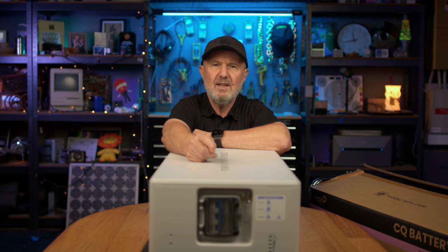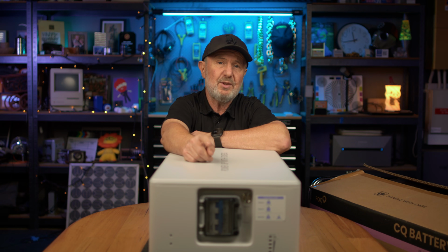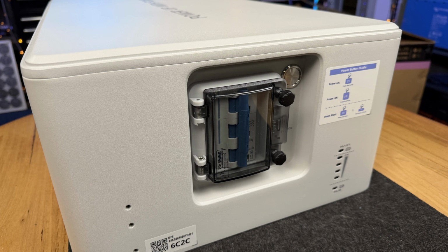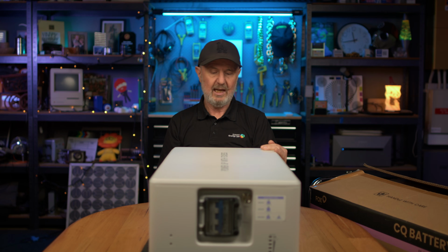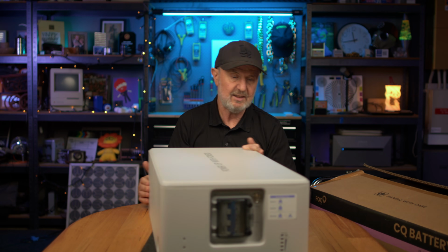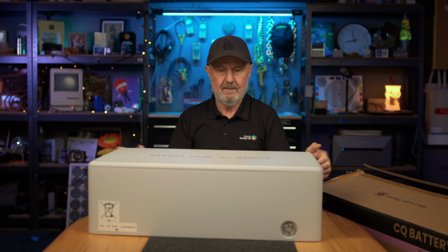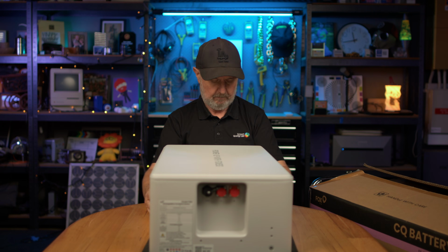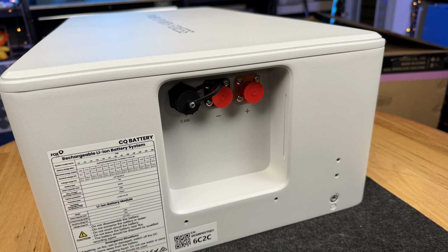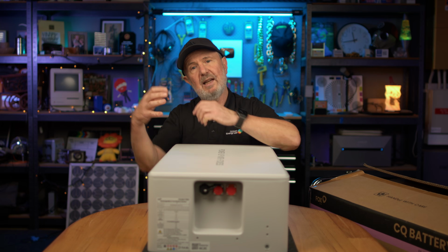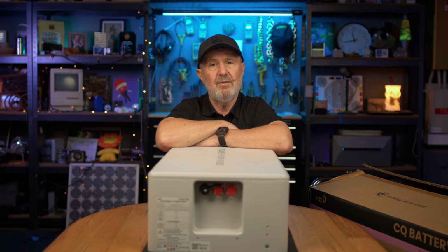As you can see at the end here is a circuit breaker, which provides you with the required overcurrent protection adjacent to the battery system, and also isolation adjacent to the battery system. At this end, which is where the cables come out, our BMS connects. So if I turn it around for you, at this end we've got the positive and negative that's going to go to the inverter and the comms connection. And of course, that little cover goes over the unit there to cover those completely.